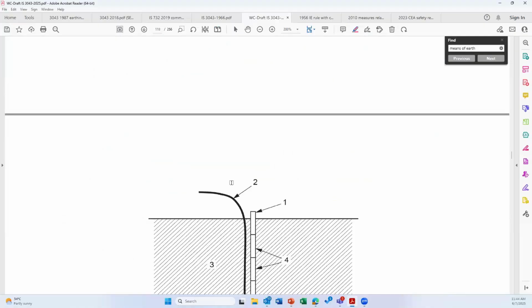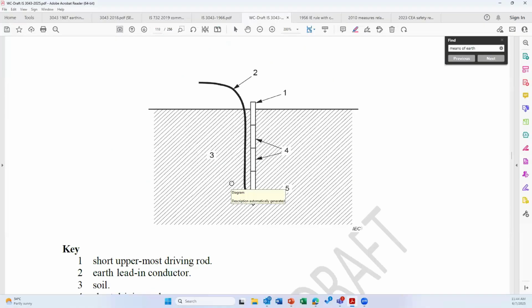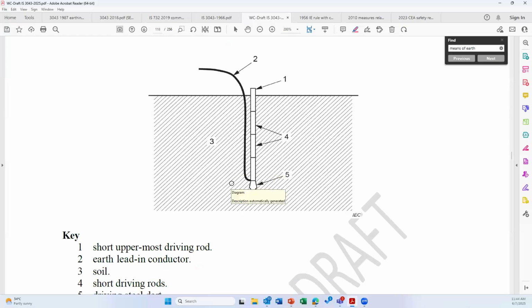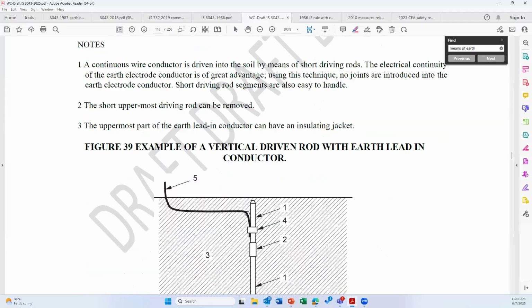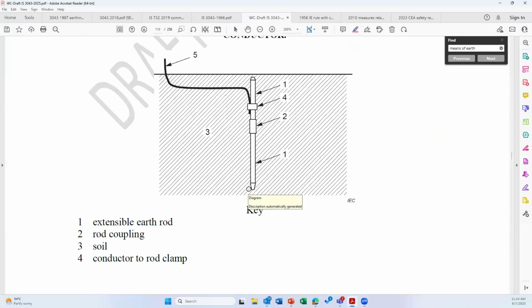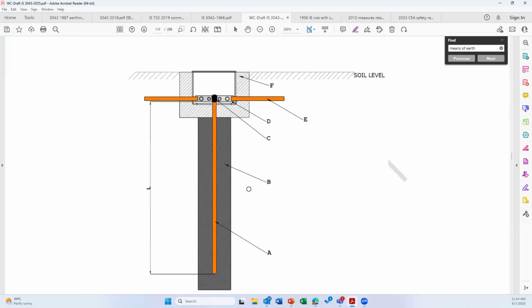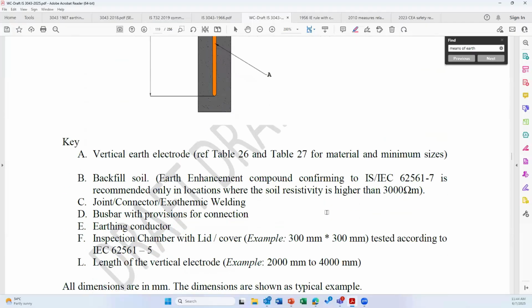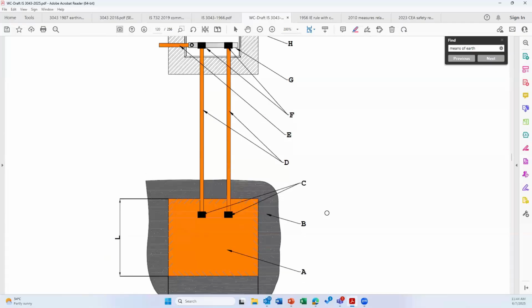Then the types of earth electrodes. What kind of earth electrodes can be used? The driven rod. The source of the figure is IEC 62305. It means a small piece of metal you can drive into the soil. Number 2 is a copper conductor. So this copper conductor will be properly inside the soil. This becomes one type of earth electrode. The second type of earth electrode, again a driven rod. The third is again the same old information, the vertical rod in a bored or buried hole, and the plate.